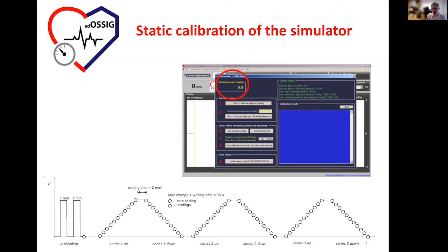So here on the y-axis is pressure, on the x-axis is time. We are measuring the errors in 11 points here, and then 11 points here, and again 11 points here, and up and down. We are using these 3 series because with them we can also calculate errors because of the hysteresis of the device. We can calculate the repeatability of the device and stuff like this.